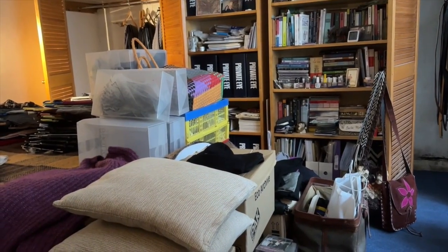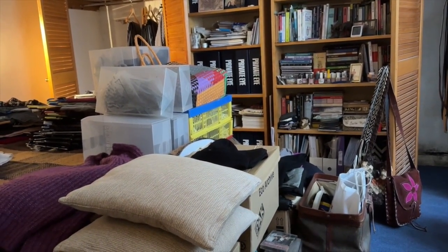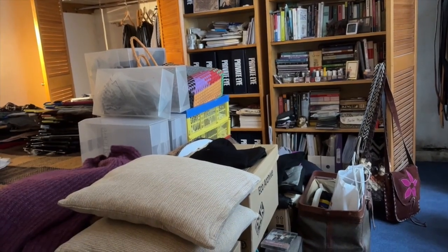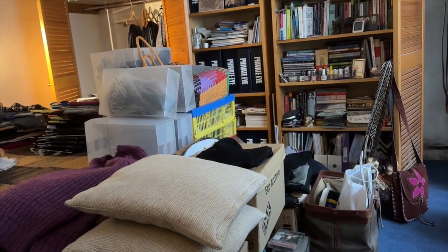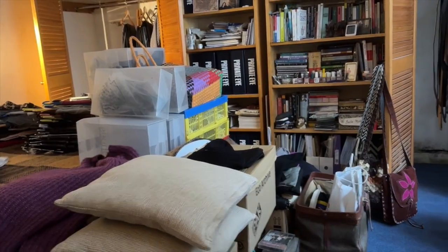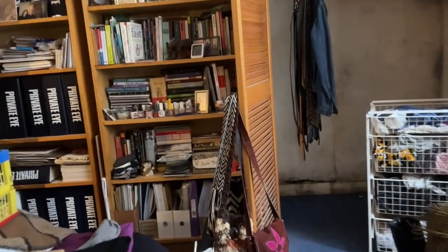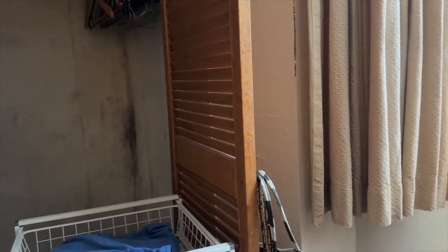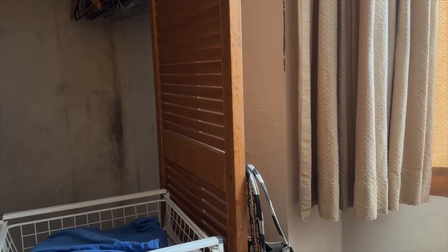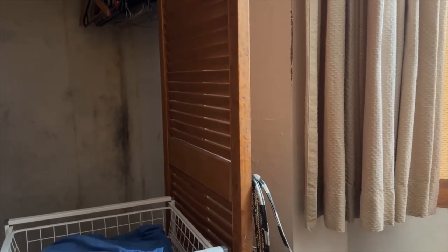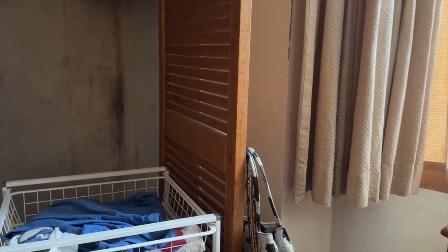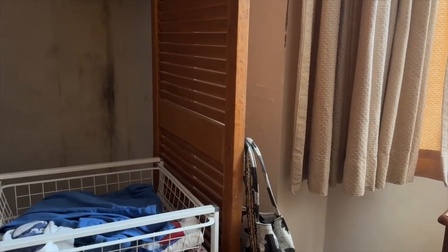It's a combination of excess vapor, which is the primary cause, from insufficient ventilation or dehumidification, made worse by poor airflow, because behind the cupboard you're not going to get much airflow. And because the cupboards are all on the external wall, and it was originally a party wall, and you've got those buttresses on the outside that cause extra heat loss.